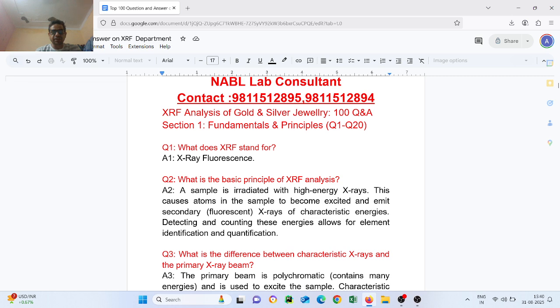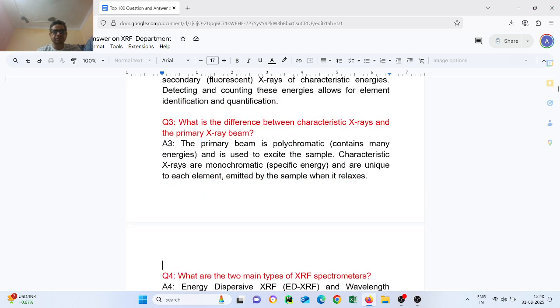Question number 3: what is the difference between characteristic X-ray and the primary X-ray beam? The primary beam is polychromatic, containing many energies, and it is used to excite the sample. Characteristic X-rays are monochromatic, with specific energy, and are unique to each element, emitted by the sample when it relaxes.